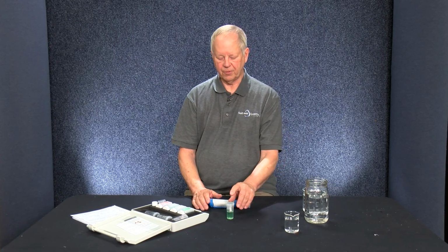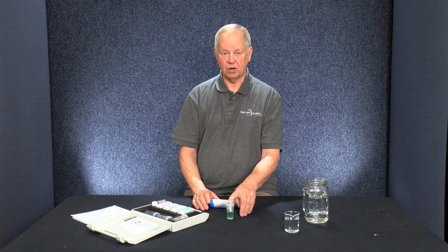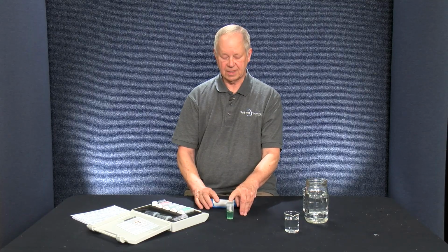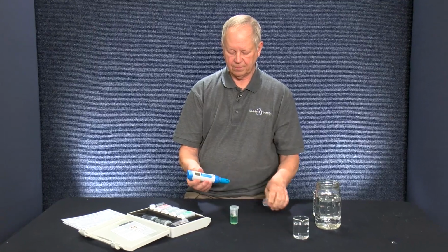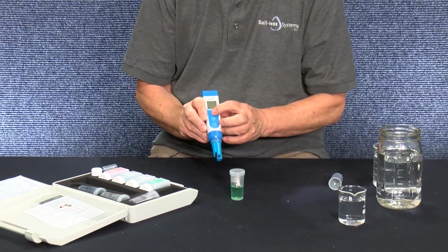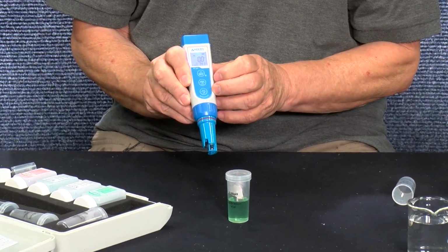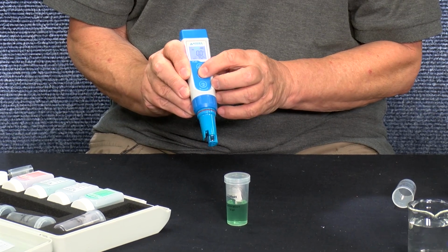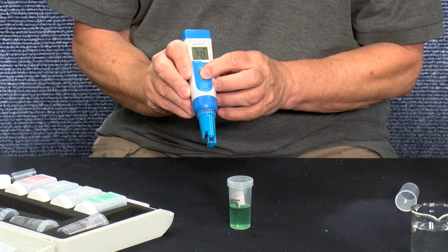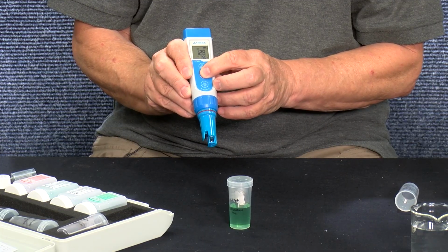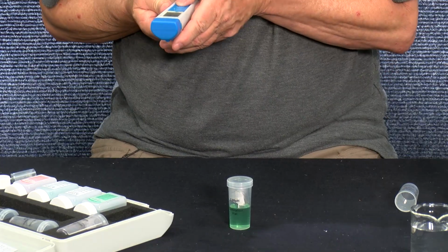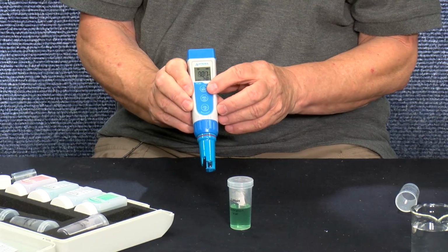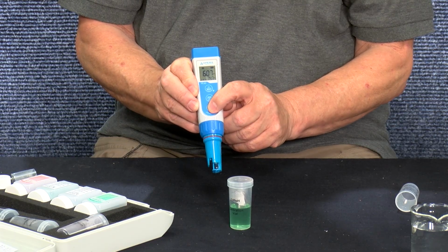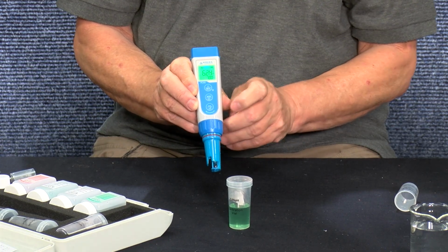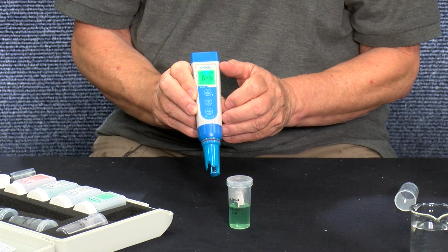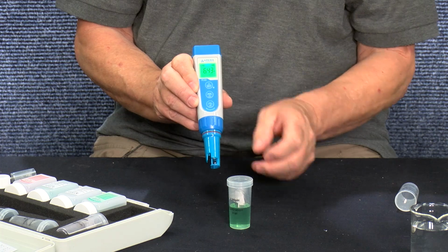So we're starting off with the 7.0 on the pH. You always start with pH, then go to EC. And you always start with 7. You take your meter, and you power on. Click your mode switch till you make sure it's in pH. I'm just going to keep clicking until I find it. And then we hit calibrate. You notice the screen turns green, and it's going to request that the first pH be 7.0.